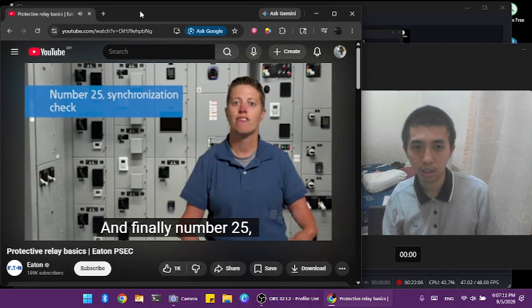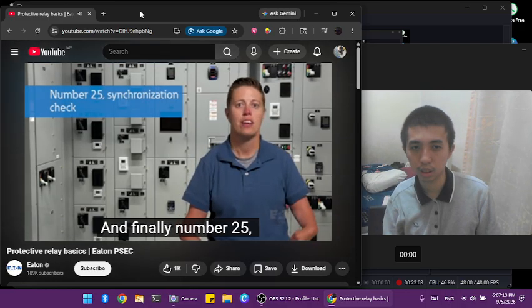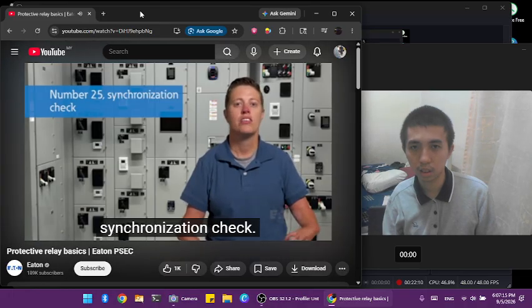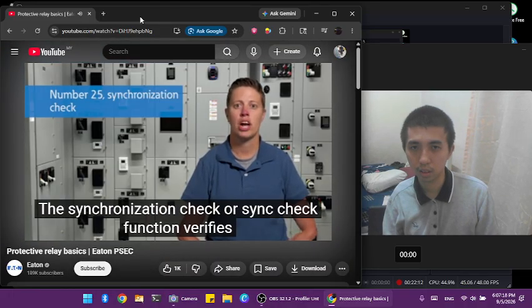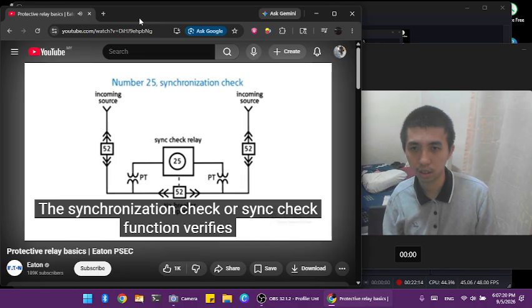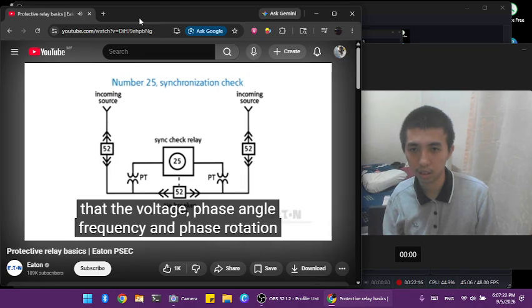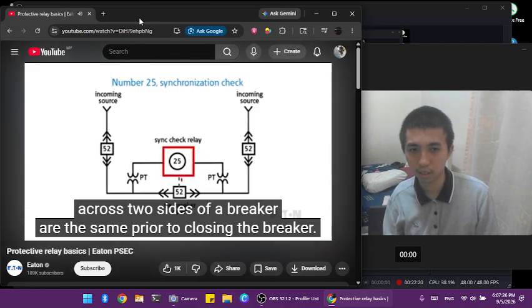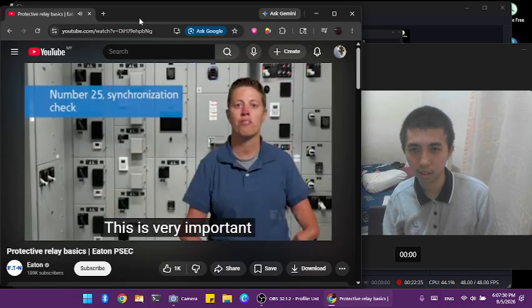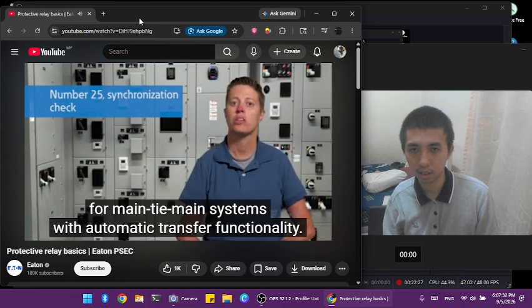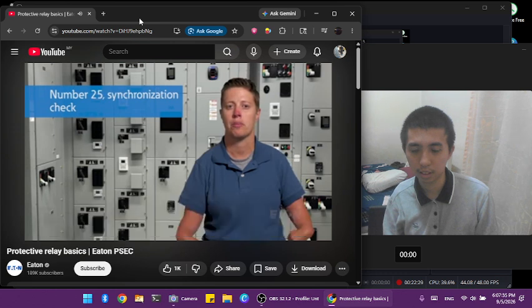And finally, number 25, synchronization check. The synchronization check, or sync check function, verifies that the voltage, phase angle, frequency, and phase rotation across two sides of a breaker are the same prior to closing the breaker. This is very important for main-tie-main systems with automatic transfer functionality.